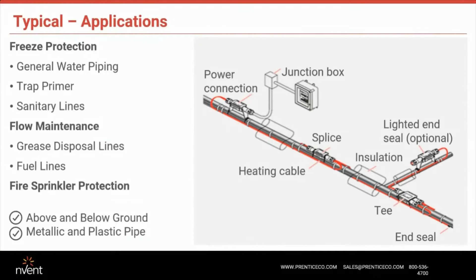Flow maintenance: anything from a greasy waste line to a fuel oil line, anytime you're trying to elevate pipe temperature. Things you guys might see out in the field that you don't think about, but could make your customers aware of, like caustic, which I find commonly isn't heat traced, and it really should be maintained at a higher temperature, typically 50 to 60 degrees. Otherwise, it starts to become very difficult to flow through your pumps. Another application that's fairly new is the NFPA 13 fire sprinkler protection systems, so we do offer heat trace that can now solve those applications as well.